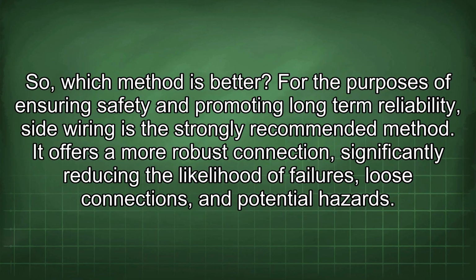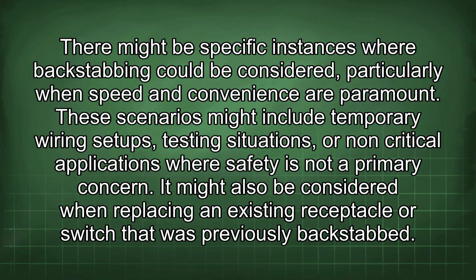So, which method is better? For the purposes of ensuring safety and promoting long-term reliability, side wiring is the strongly recommended method. It offers a more robust connection, significantly reducing the likelihood of failures, loose connections, and potential hazards. There might be specific instances where backstabbing could be considered, particularly when speed and convenience are paramount. These scenarios might include temporary wiring setups, testing situations, or non-critical applications where safety is not a primary concern. It might also be considered when replacing an existing receptacle or switch that was previously backstabbed.